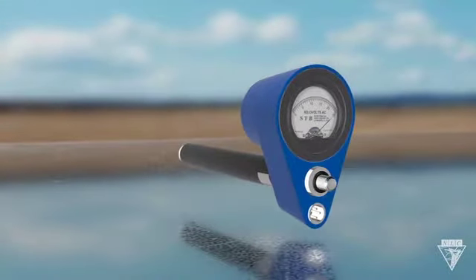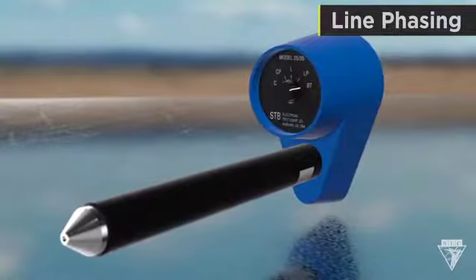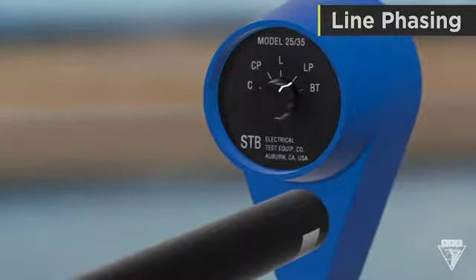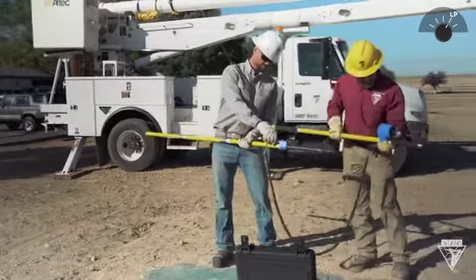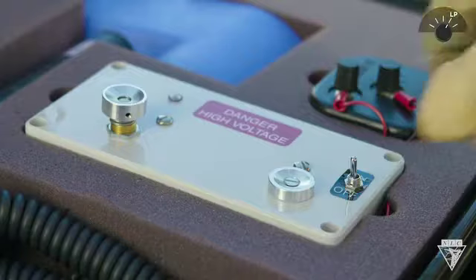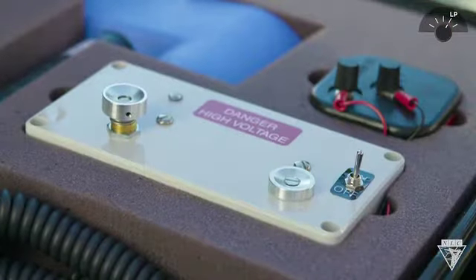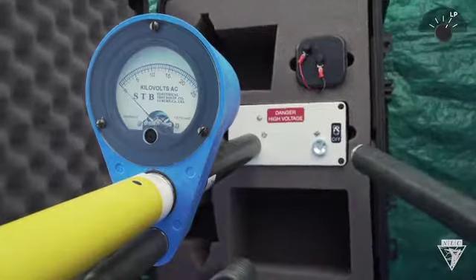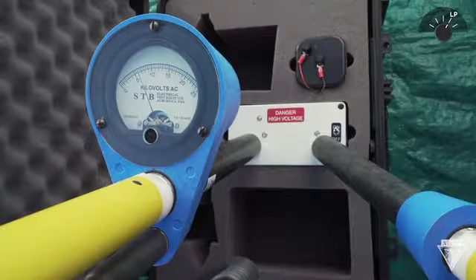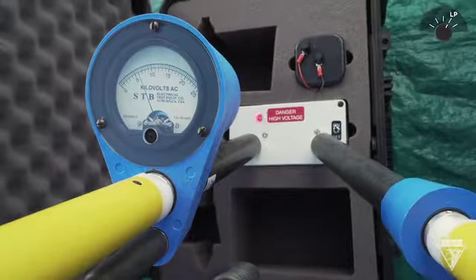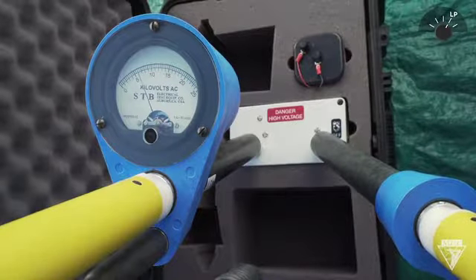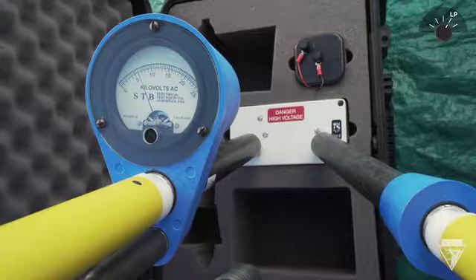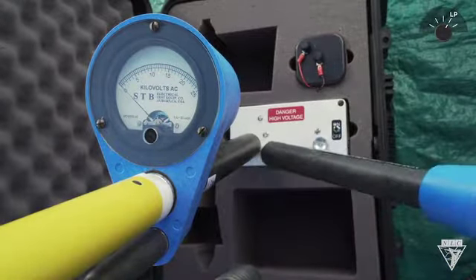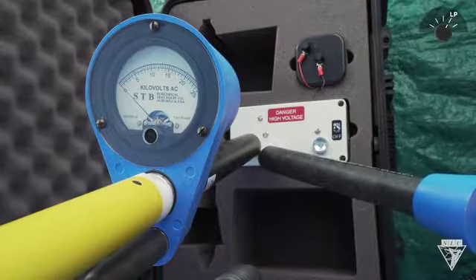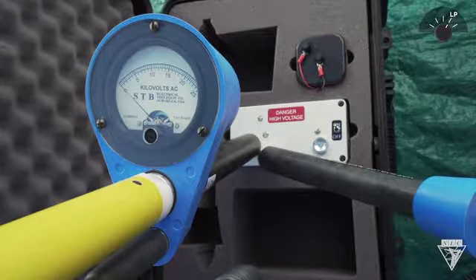To proof test the meter for direct line contact, set the dial to LP, line phasing. Then install the phasing cable and probe and turn on the included tester. Touch the phasing probe to the stationary washer and push down on the raised washer with the meter probe until the red light glows. The needle should deflect between 3 and 6 kV. Next, use both probes to push down on the raised washer. The needle should now read less than 2 kV.